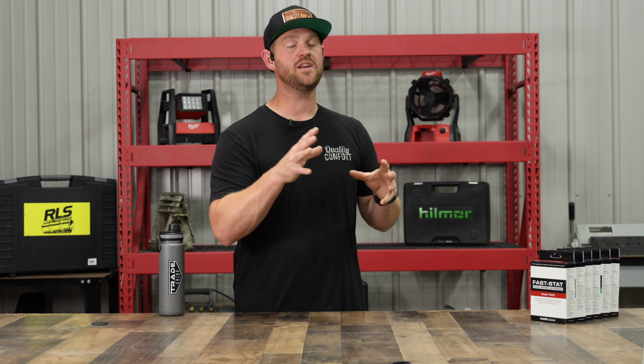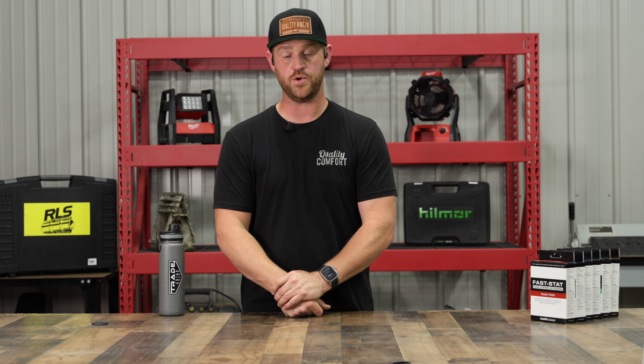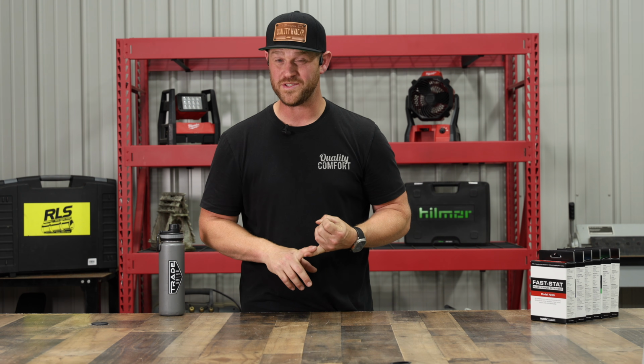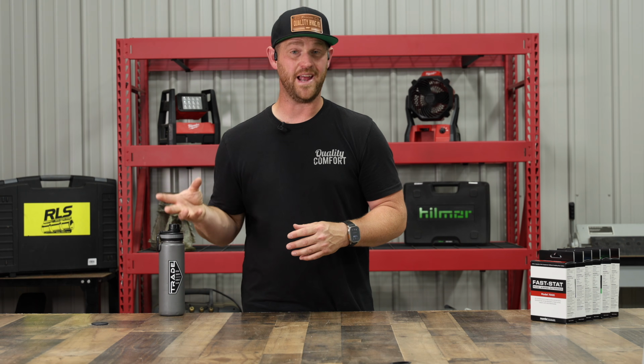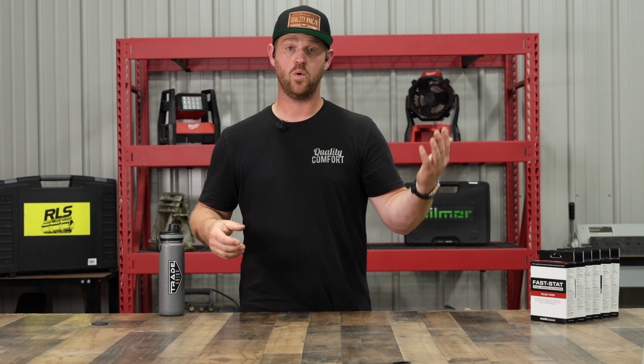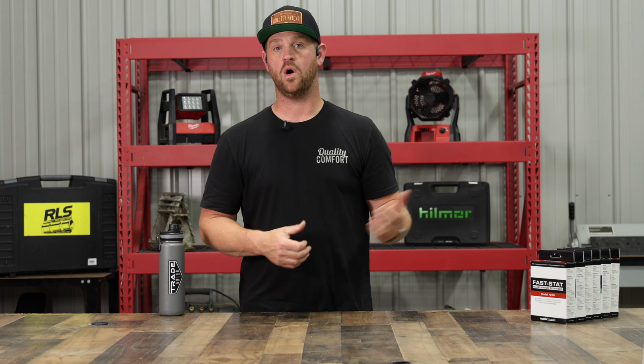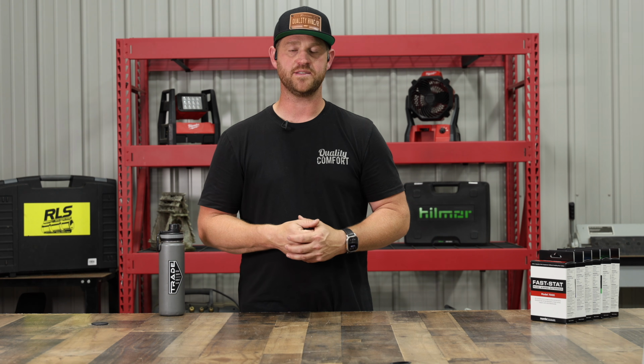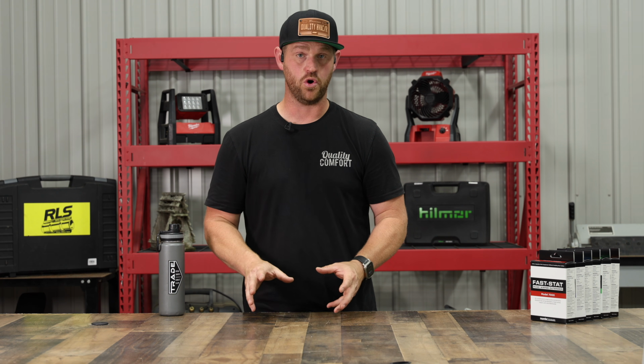So that's going to go to the next portion, the different types of equipment that are available. Because when it comes to variable speed, there are actually quite a few different options. You have 24-volt controlled systems. That's the one I was just talking about with the thermostat, where you can lock it out with your outdoor sensor. Honeywell makes one, Pro One makes one. There's a bunch of different brands that offer that type of control.